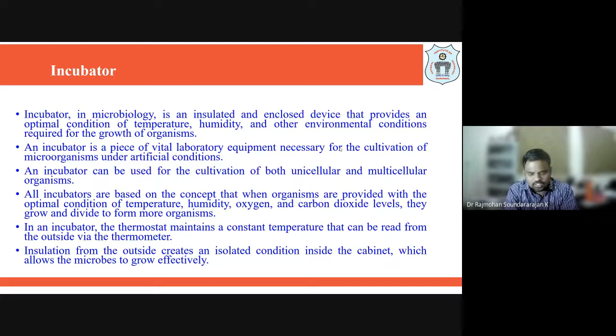They are based on the concept that when the organisms are provided with the optimum conditions of temperature, humidity, oxygen, CO2 levels, they grow and divide to form more organisms more efficiently, right? So also in an incubator, a thermostat will be there which will maintain a constant temperature, which you can read through a display meter. Also, it is insulated from the outside, which creates an isolated condition inside the cabinet, which allows the microbes to grow efficiently. And other than temperature, parameters like humidity and airflow are also maintained using different mechanisms that will give an environment similar to a natural environment that is required for a microorganism to grow more effectively.